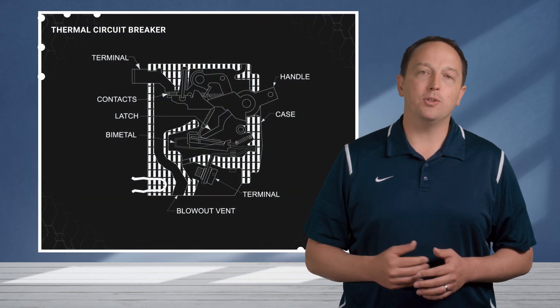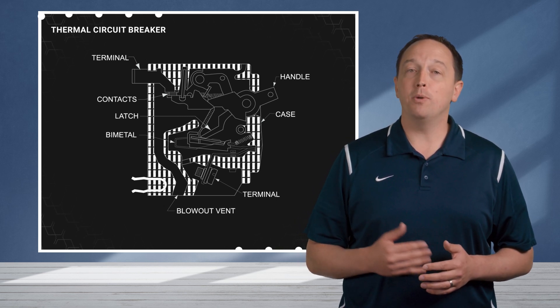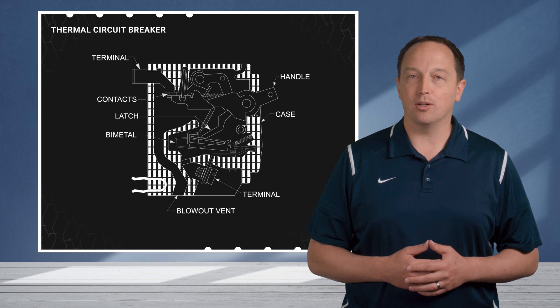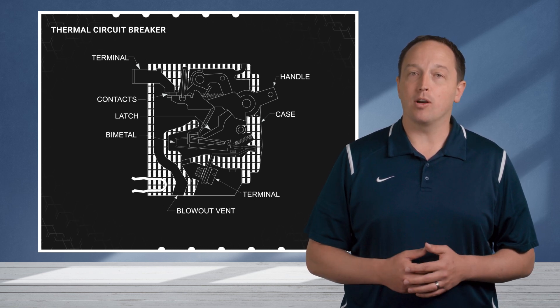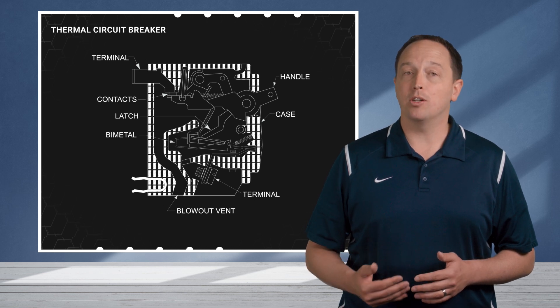A thermal circuit breaker uses a thermal sensing element, often called a bimetal, that is designed to deflect and open the circuit breaker at a predetermined temperature. Current flowing through the element causes I2R heating, and the current capacity is determined by the size, shape, and construction of the element.